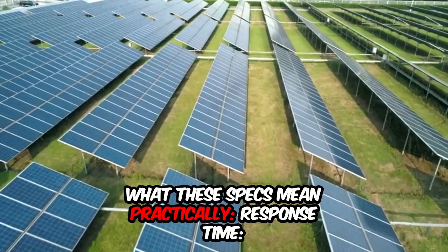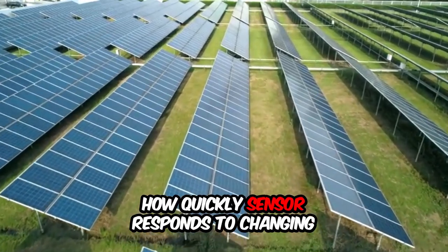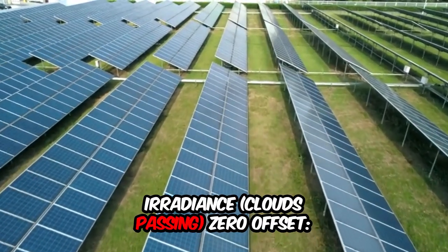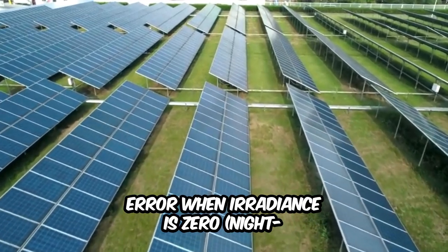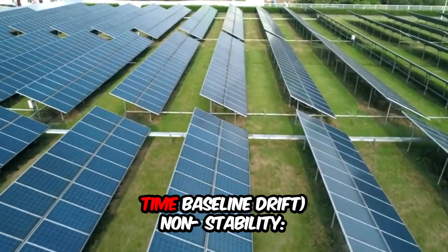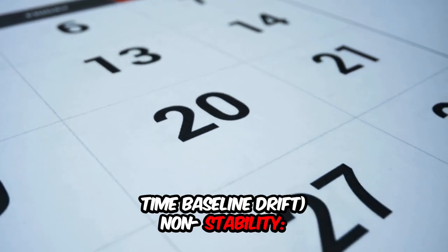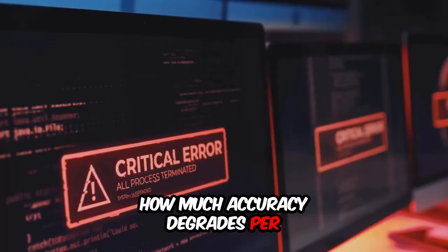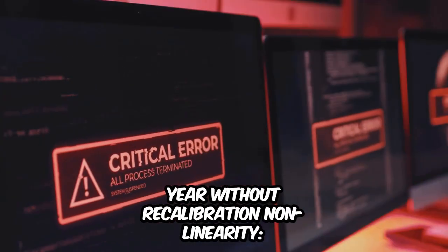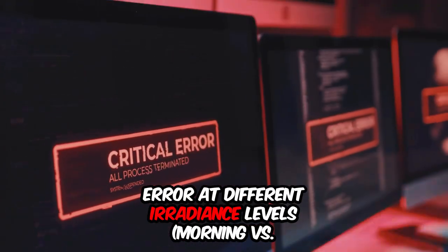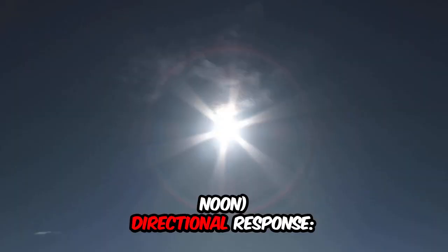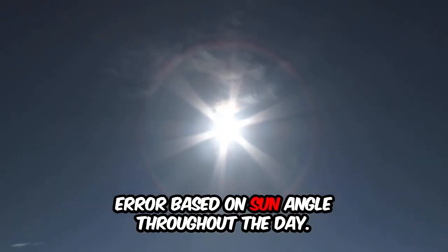What these specs mean practically: response time, how quickly the sensor responds to changing irradiance, such as clouds passing. Zero offset error, when irradiance is zero, the nighttime baseline drift. Non-stability, how much accuracy degrades per year without recalibration. Non-linearity, error at different irradiance levels, morning versus noon. Directional response, error based on sun angle throughout the day.